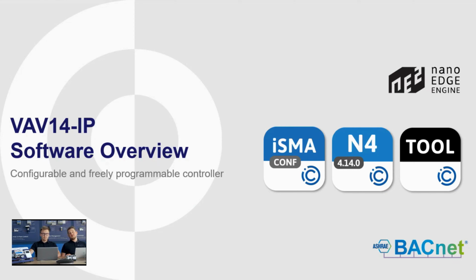Let's maybe now look at what we bring from the software standpoint. We thought about multiple ways of how you as the users would like to configure, commission, and balance the VAV system. And therefore, we bring multiple tools and multiple ways to configure the built-in application in the controller. But that's not all. Together with the controller, because of the Nano Edge engine itself, we give you tools to program the controller either with Niagara Workbench or VAV tools. So altogether, we bring you a number of tools for the configuration, commissioning, and balancing of the entire VAV system. So let's maybe first look at the application itself.